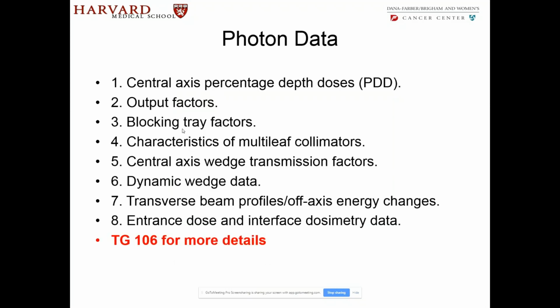So what kind of data do we take? Well, we have the central axis PDD, of course. Then you have output factors. If you're using blocking trays, then you need the tray factors. Multi-leaf collimators, you want to check the characteristics of that. Central axis wedge transmission factors, dynamic wedge data, transverse beam profiles, off-axis energy changes, whatever they might be, entrance dose, and interface dosimetry data. All this is listed in proper form in the Task Group 106 report that you can refer to for more details. I'll send that as well.